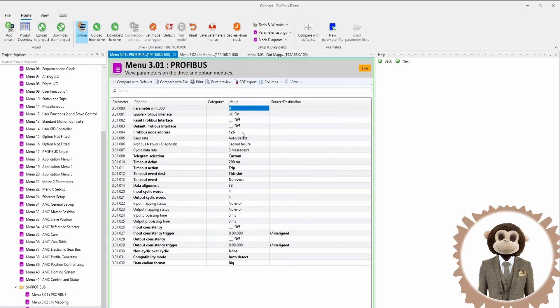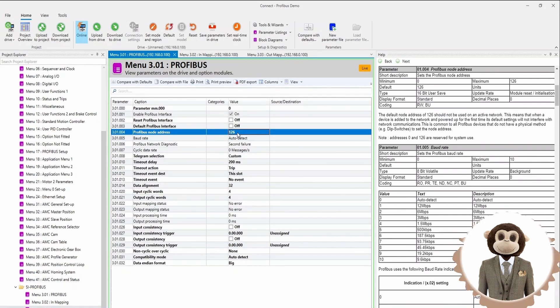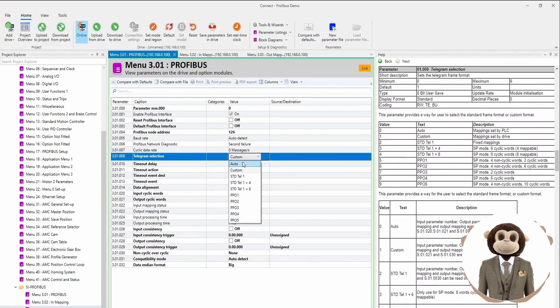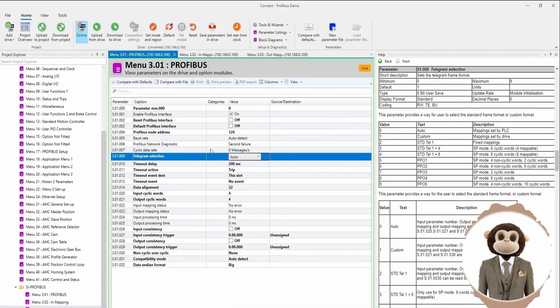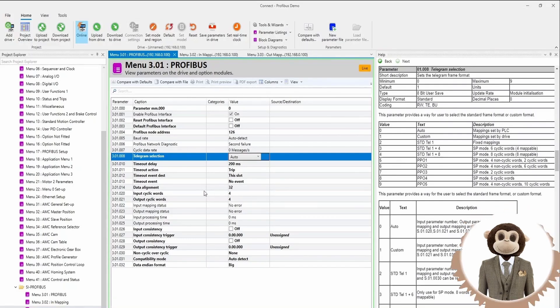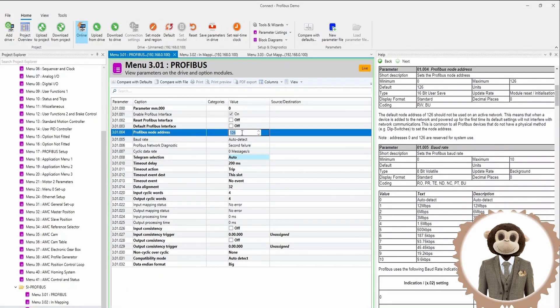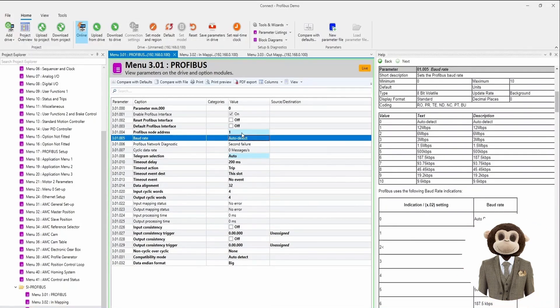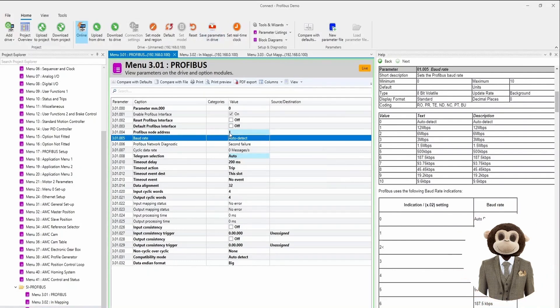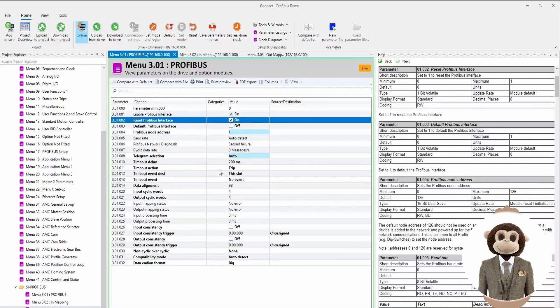From here we have to set up the PROFIBUS node address and set the telegram selection to auto, meaning that the PLC is going to tell the drive the input and output mappings, as well as data alignment and the number of input and output words it will be reading and writing. We're going to set the PROFIBUS node address to node address one, save our parameters, and then reset the PROFIBUS interface.